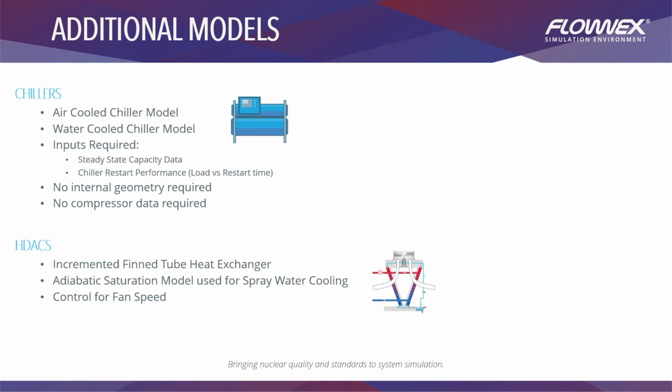So we've developed a reduced order model that uses the steady state capacity data of the chiller and the chiller restart performance. This is information that is possible to get from chiller manufacturers and gives a comparably good accuracy for the amount of data that's required.